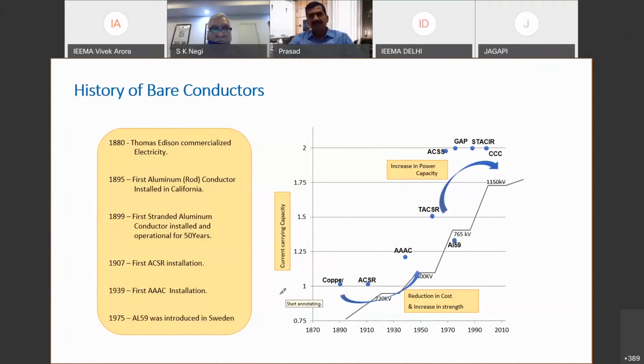Over the period of time, with new innovations and technological developments, we could find from site data that ACSR has two metals inside. One is the galvanized steel, most probably, and EC grade aluminum wires. So it was making a bimetal kind of combination. So whenever this conductor was exposed to a corrosive environment or industrial pollutant environment, one metal was becoming anode, the second was becoming cathode, and there was some galvanic corrosion happening, and that was drastically reducing the life of the conductor due to corrosion. At the same time, due to the steel inside, it was a little bit heavy.